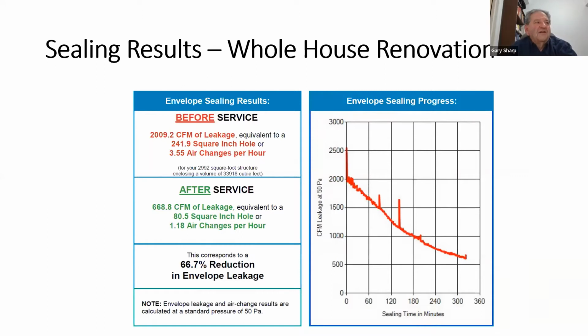And so this one started off at 2,000 CFM of leakage, 242 square inch holes, so 24 by 10, and 3.55 air changes per hour. And when we finished after 5.5 hours, the leakage was down to an 80 square inch hole, so 8 by 10 from 24 by 10.